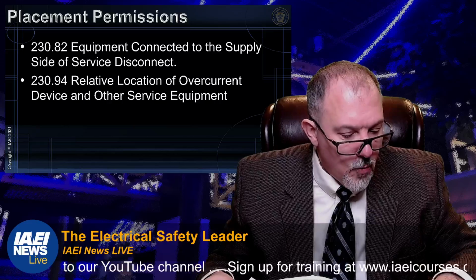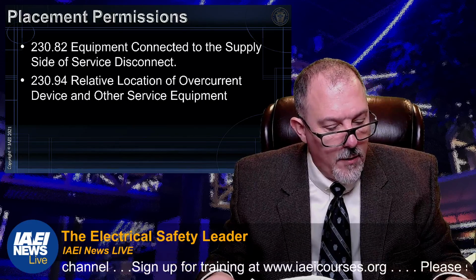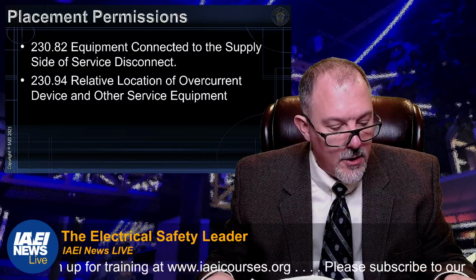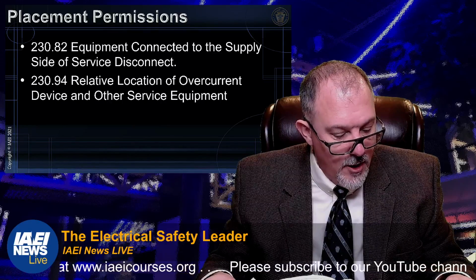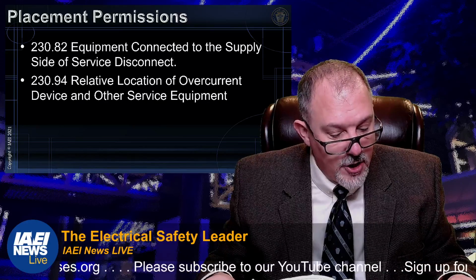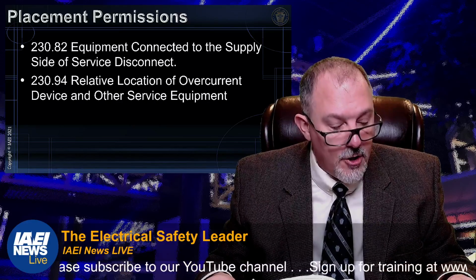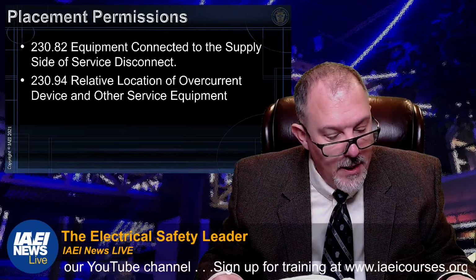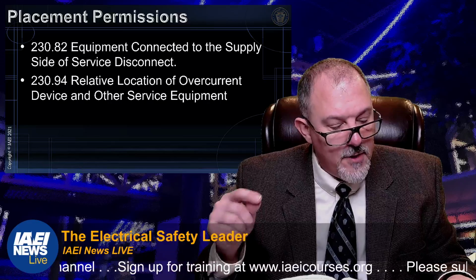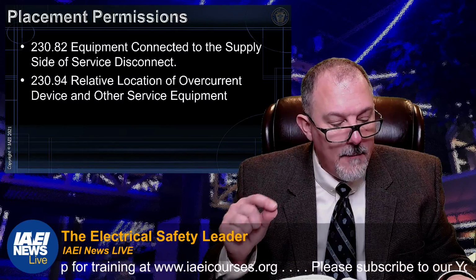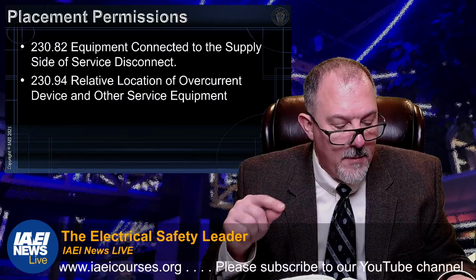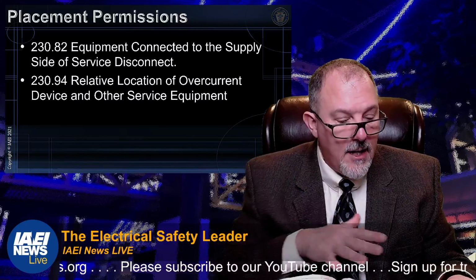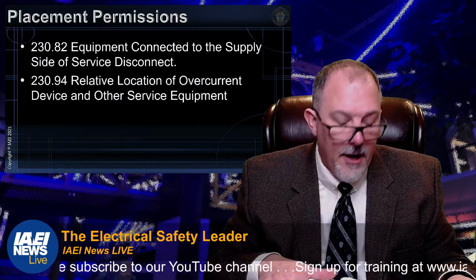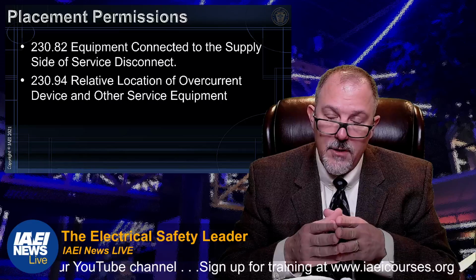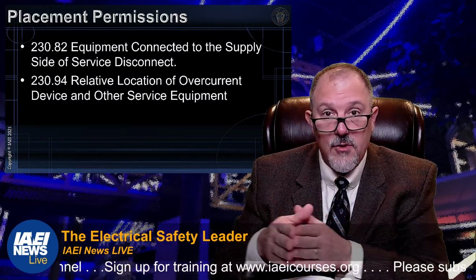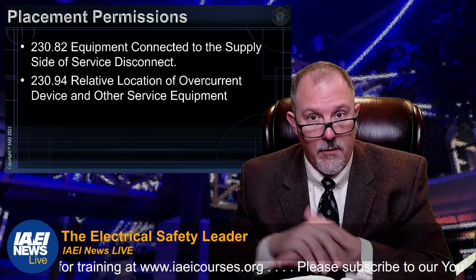And then 230.94, relative location of overcurrent device and other service equipment. The overcurrent device shall protect all circuits and devices. There is an exception. Drum roll, please. High impedance shunt circuits, surge arresters, Type 1 surge protective devices. Where do we say Type 1 would be? On the line side. Surge protective capacitors and instrument transformers, current and voltage, shall be permitted to be connected and installed on the supply side of the service disconnecting means as permitted by 230.82. So 230.94, this is relative location of overcurrent device and other service equipment. And then you don't treat those as a service overcurrent protective device, even though they're on the line side. If they're serving these functions, they're not treated as a service overcurrent protective device.